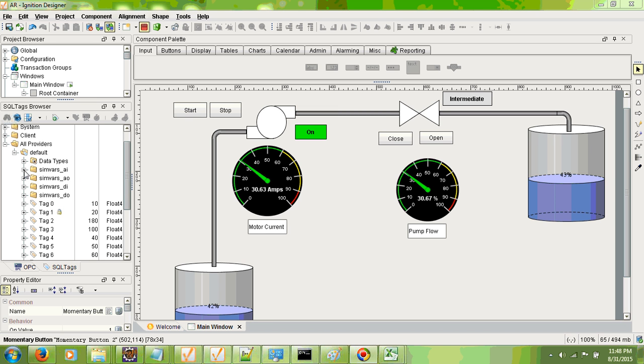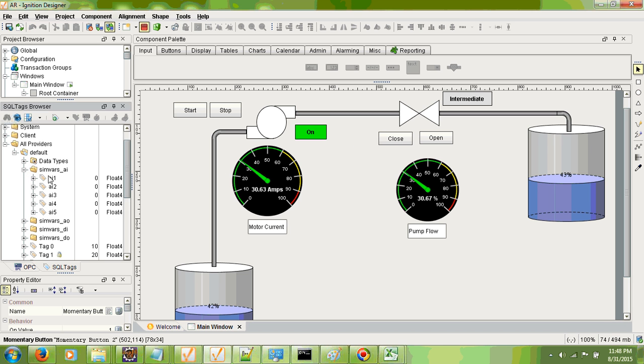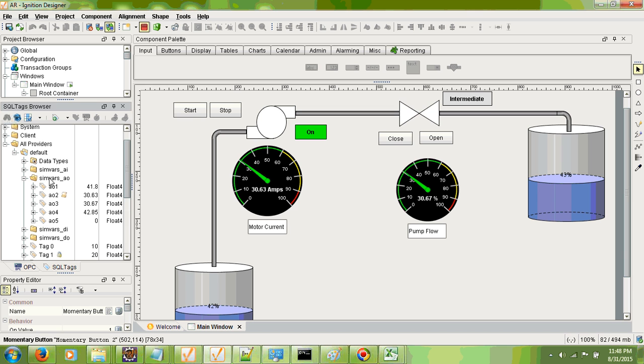We have defined folders in the Ignition database for the analog inputs coming from the SCADA system to the simulation system. This folder is for analog inputs — obviously there are no analog inputs in this system but we have defined five floating point tags, they are not used. The next folder is for analog outputs: analog output 1 is tank one level, analog output 2 is motor current, analog output 3 is pump flow.